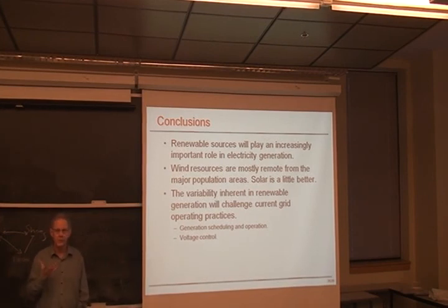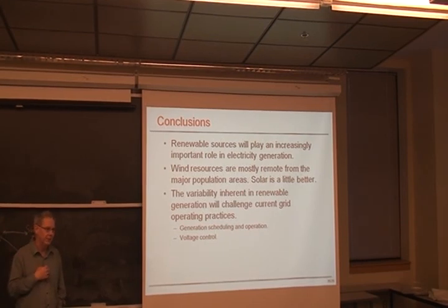So you could build 25%, but when it goes away, you would need significant interconnection capability with the neighbouring states, and the existing transmission wouldn't be capable of meeting that increase in flow from the neighbours.